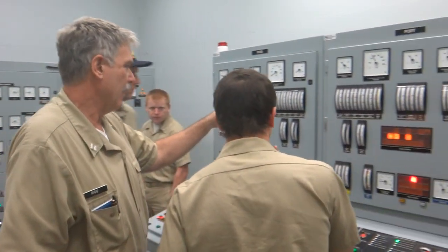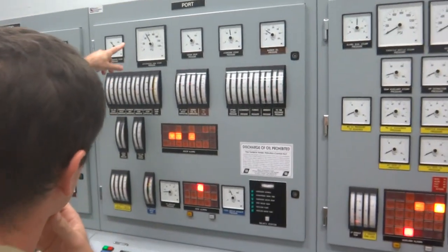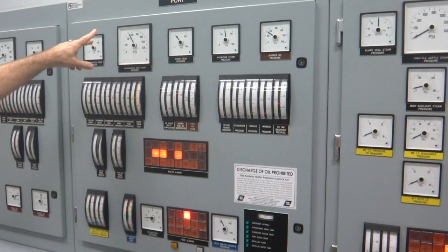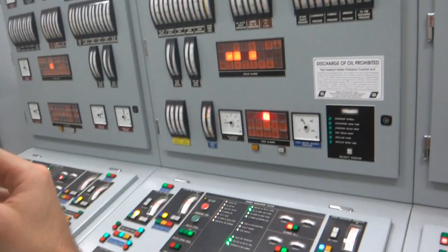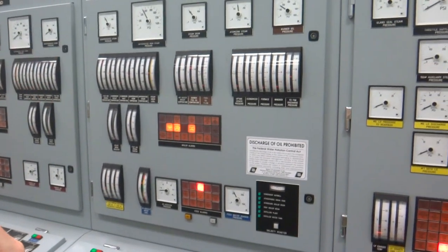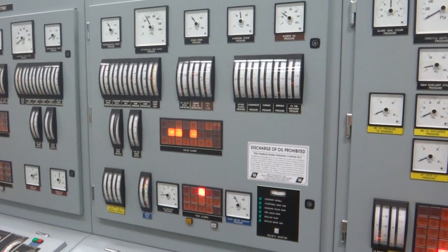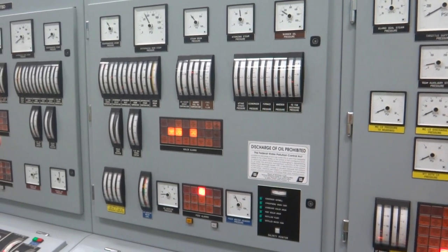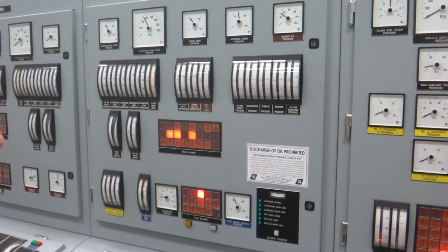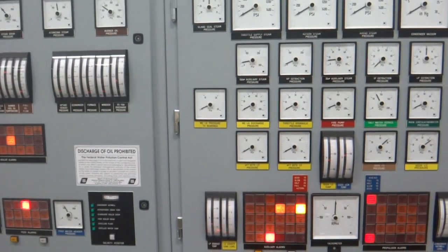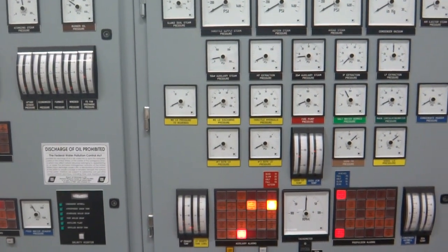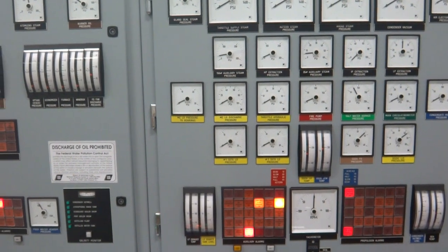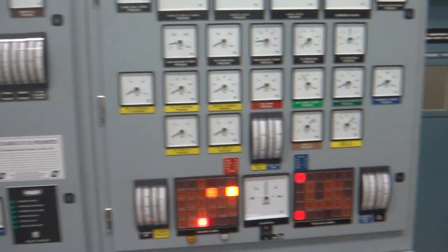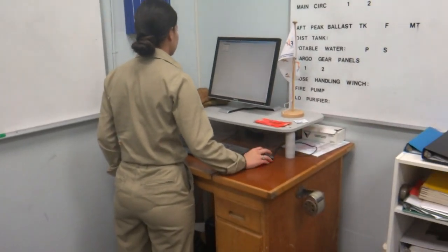We got a turbine feed pump on, water level's good. We got just over 500 PSI, but we're probably going to have that drop as soon as we start warming up the 150 pound, which isn't showing anything at the moment. And you're 35? What's up with that? Oh, control air. Good point. First, who's our first? Control air. Get the control air on, and then that'll make a difference.